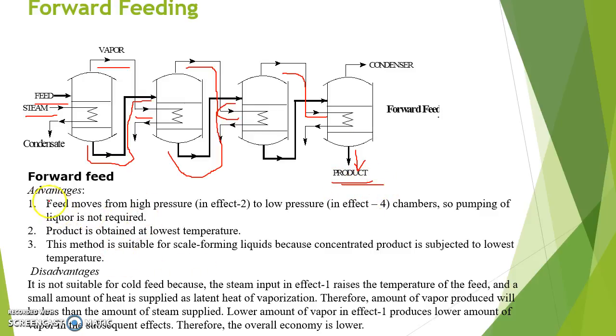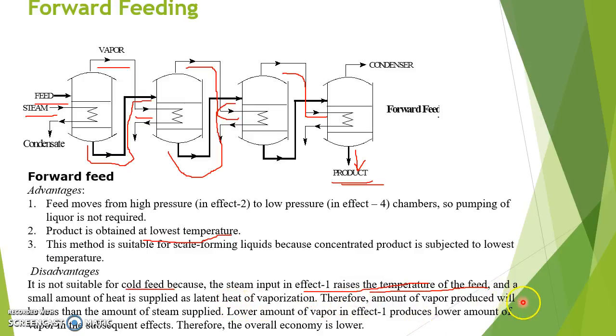Advantages of forward feeding: feed moves from high pressure to low pressure chamber, so pumping of liquor is not required. The product is obtained at the lowest temperature. This method is suitable for scale-forming liquids because the concentrated product is subjected to the lowest temperature. Disadvantages: it is not suitable for cold feed, because the steam input in effect 1 raises the temperature of the feed, and only a small amount of heat is supplied as the latent heat of vaporization. Therefore the amount of vapor produced will be less than the amount of steam supplied, and the overall economy is lower.